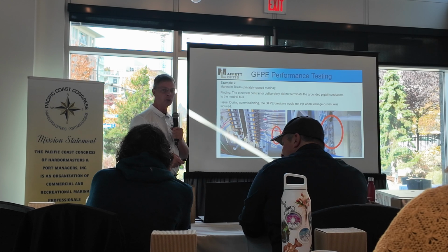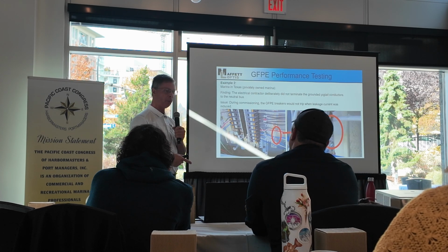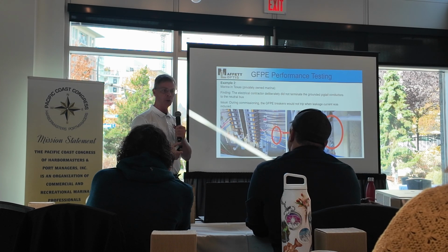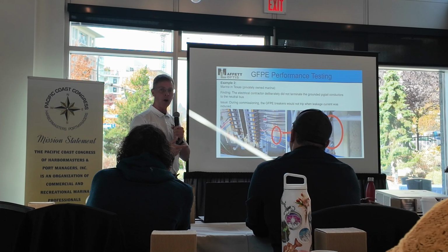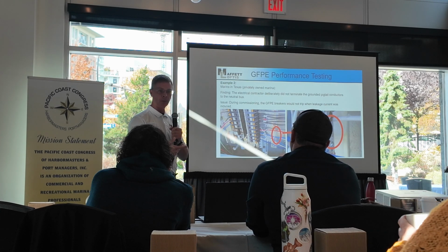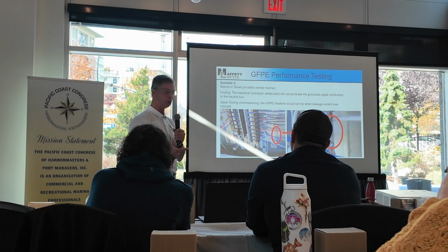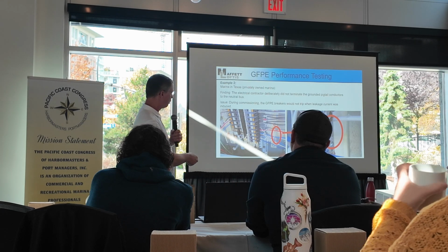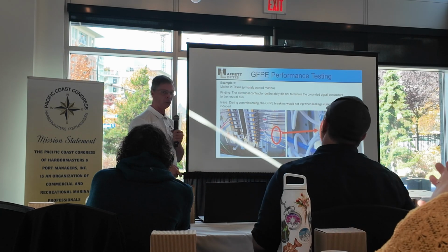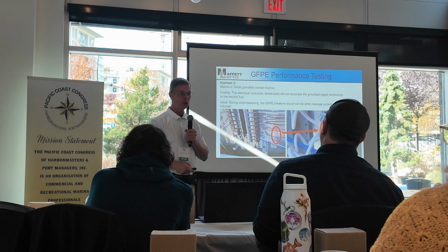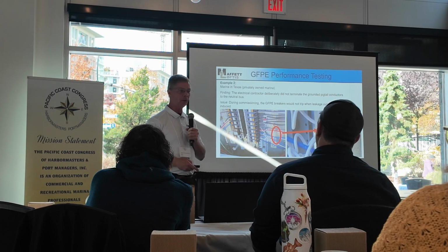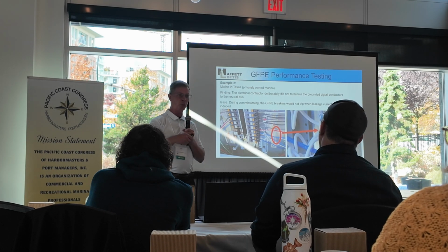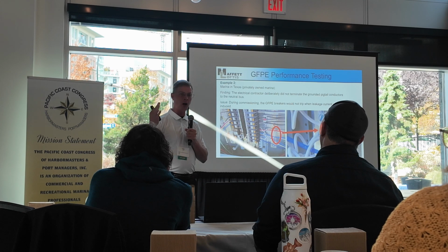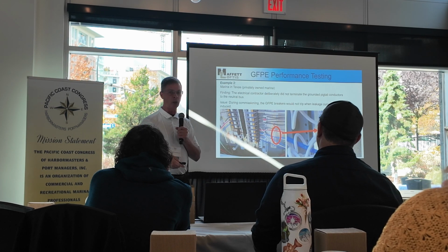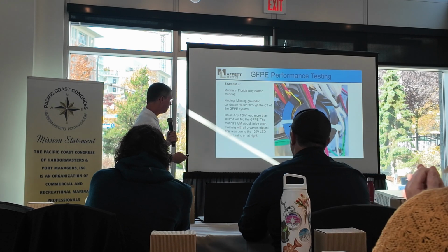This is actually criminal, because when I went to test, every single 30 milliamp GFPE breaker would never trip. Even though it kept power and looked good, polarity was good, the hot, neutral and grounds were wired correctly, it would not trip the GFPE breakers, and that was with the test buttons for them. So the performance testing was absolutely necessary. And because they shared neutrals, they had to take out all the wire for 3 different dots and rewire 3 dots. They tried to cut corners, and they wound up paying for it.